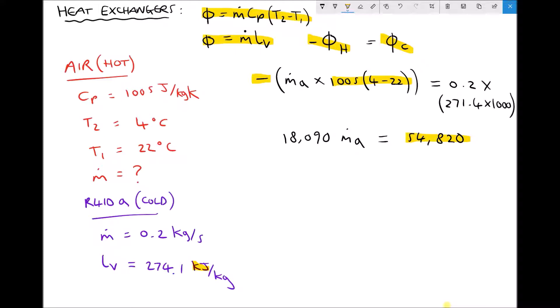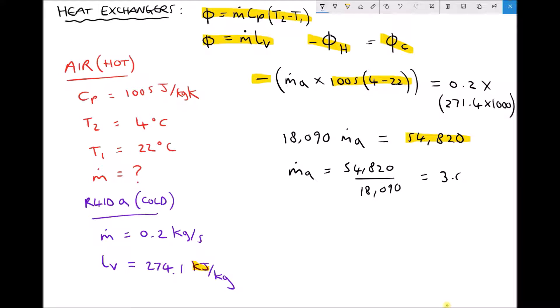Assuming the heat exchanger is 100% efficient, all heat leaving the hot fluid is gained by the cold fluid, so the left hand side must also equal 54,820. Dividing both sides by 18,090 gives us the mass flow rate of air: 54,820 ÷ 18,090 = 3.03 kilograms per second. Therefore our refrigeration unit is capable of processing 3.03 kilograms per second of air.